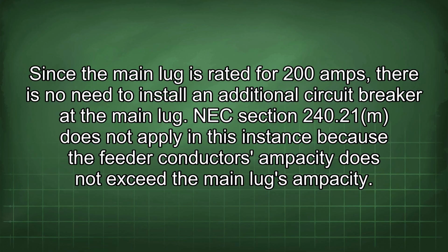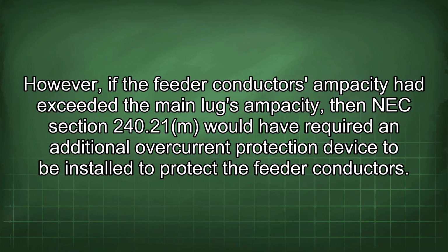Since the main lug is rated for 200 amps, there is no need to install an additional circuit breaker at the main lug. NEC Section 240.21 does not apply in this instance because the feeder conductor's ampacity does not exceed the main lug's ampacity. However, if the feeder conductor's ampacity had exceeded the main lug's ampacity, then NEC Section 240.21 would have required an additional overcurrent protection device to be installed to protect the feeder conductors.